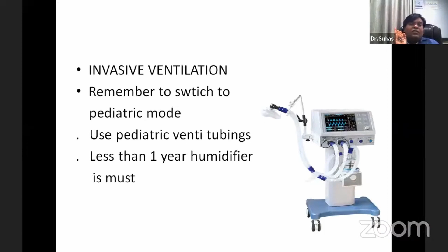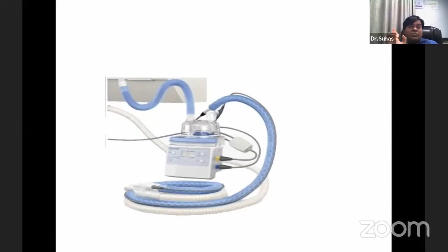So this is a humidifier. How is the humidifier attached to a ventilator? This is an inspiratory tube which is coming from the ventilator. It is going into the humidifier. From the humidifier, the inspiratory tube is going to the endotracheal tube end, and from the endotracheal tube end, the expiratory limb is coming and going to the ventilator again. And this chamber is called a humidification chamber. There is a servo control mechanism which maintains the temperature and humidity, and it humidifies the air. It also warms the air, prevents insensible water loss and the feeling of dryness of the lung, and maintains proper lung function. So humidification is very important in the pediatric age group.